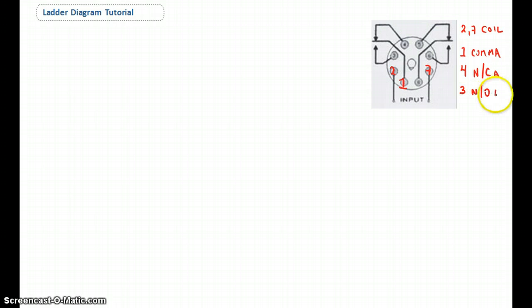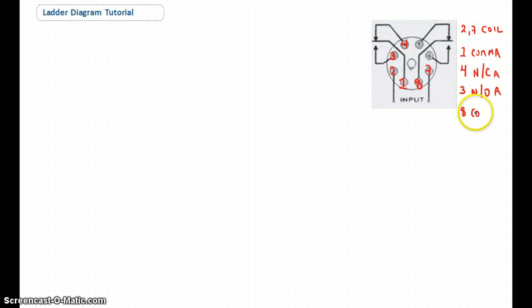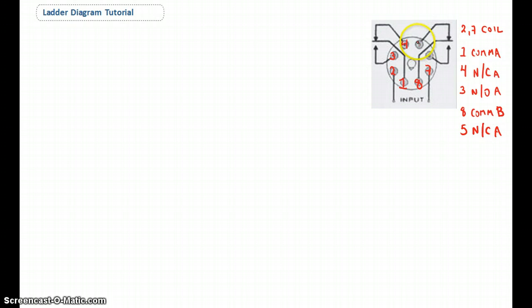So we have pins 2 and 7 for the coil, pin 1 as common A — common to both 4 and 3 — pin 4 as normally closed, and pin 3 as normally open. The other common is pin 8, that's the B part of the relay. Pin 8 is common to pin 5, which is the normally closed contact, leaving pin 6 as the normally open.